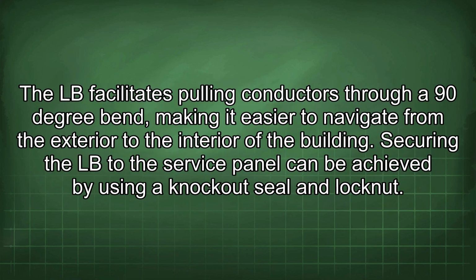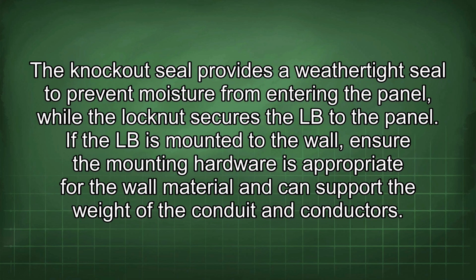The LB facilitates pulling conductors through a 90-degree bend, making it easier to navigate from the exterior to the interior of the building. Securing the LB to the service panel can be achieved by using a knockout seal and lock nut. The knockout seal provides a weathertight seal to prevent moisture from entering the panel, while the lock nut secures the LB to the panel.